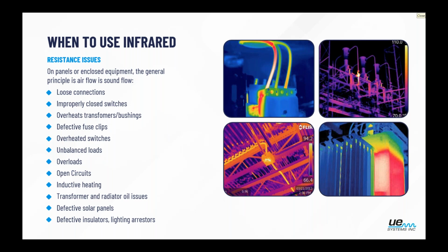And typically the most common inspected points that we're looking for are loose connections, switches that aren't closed properly, overheating within a bushing or a transformer. So that's where we would use ultrasound and infrared together, but we're looking at two different things. Fuse clips are going to be a big one. I've seen a lot of early catches on fuse clips. Overheated switches.